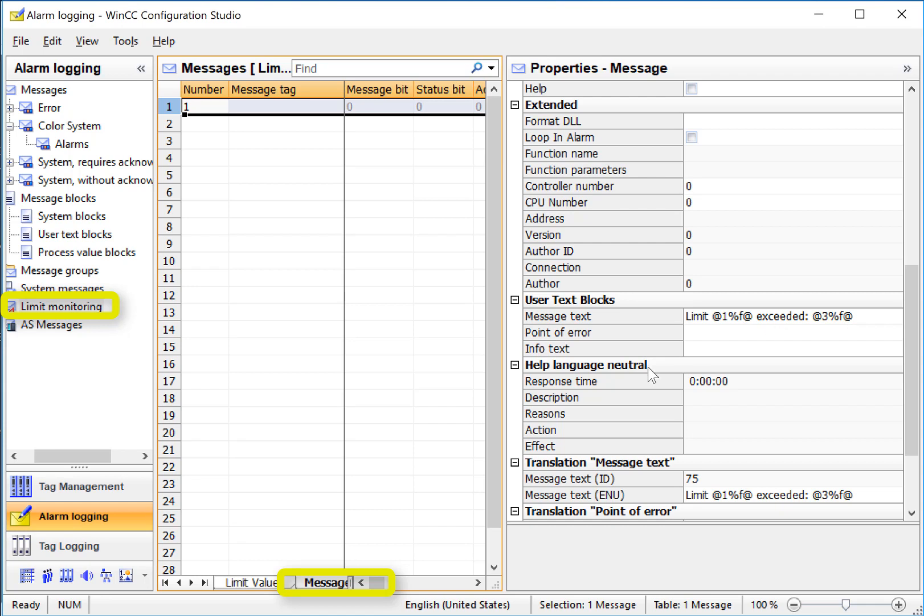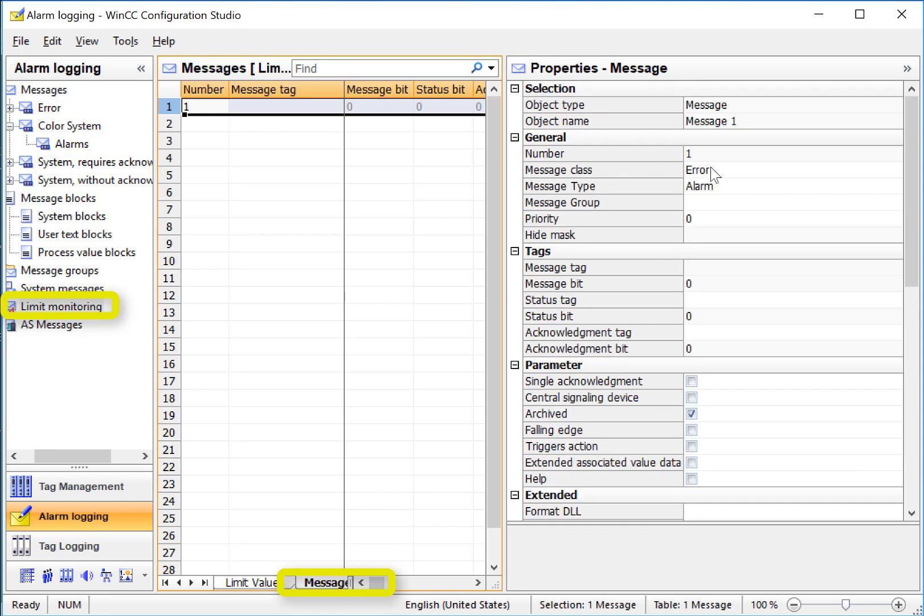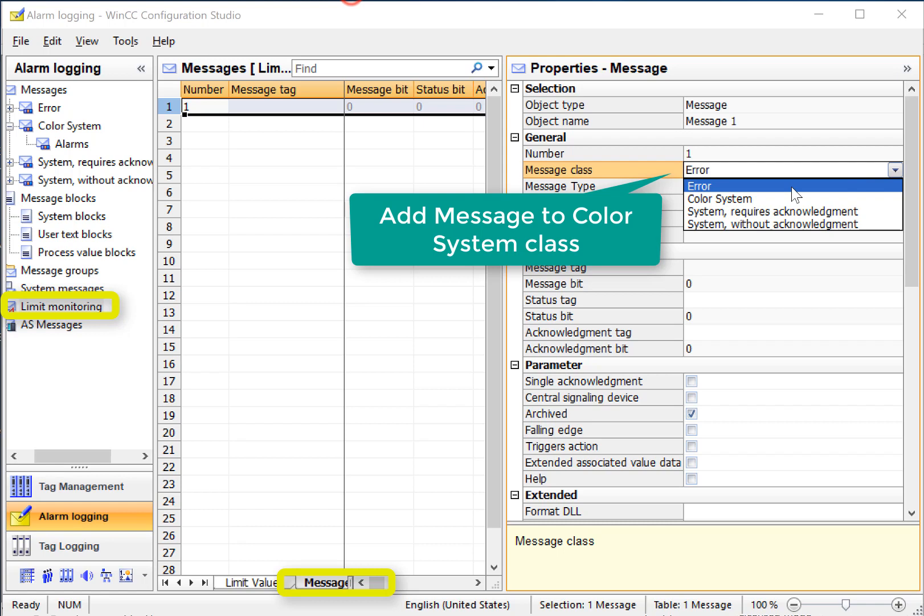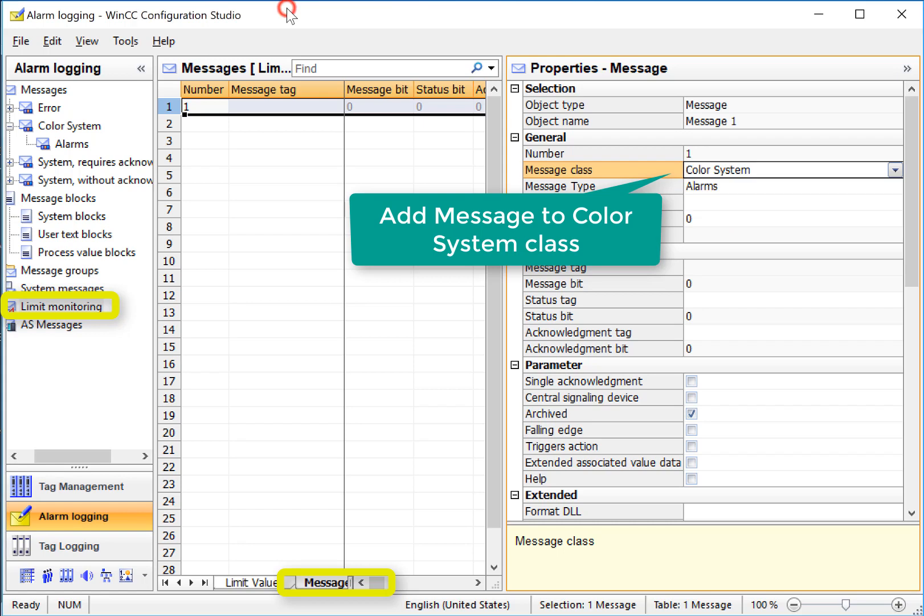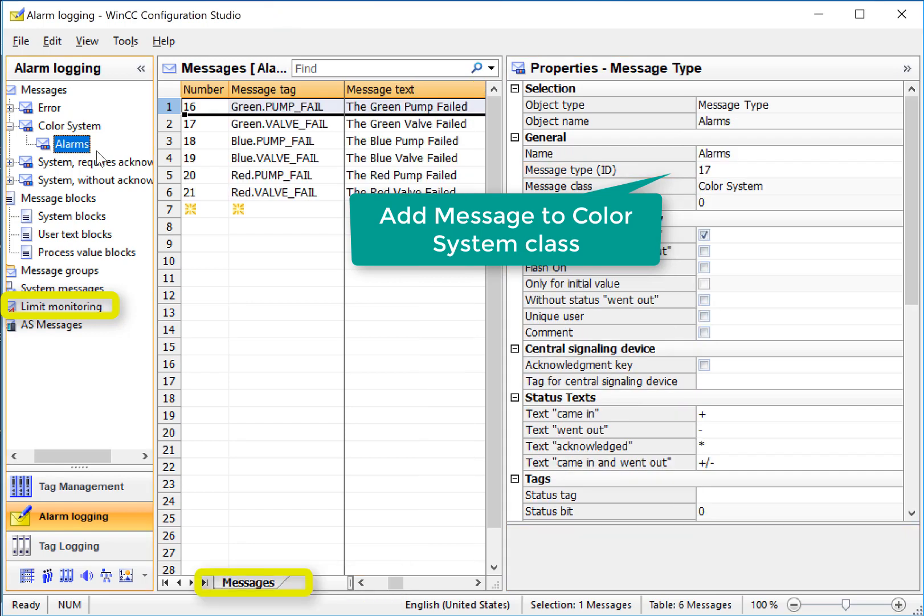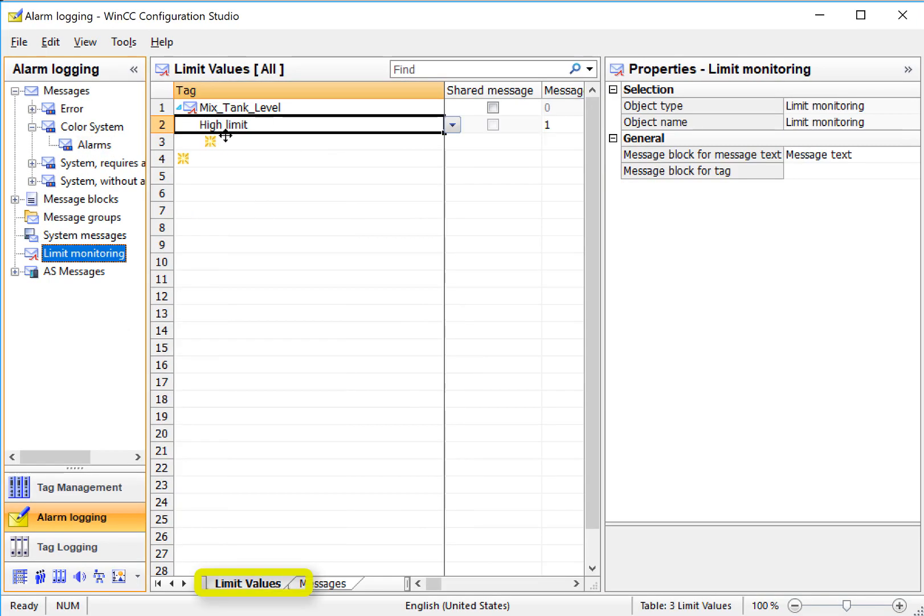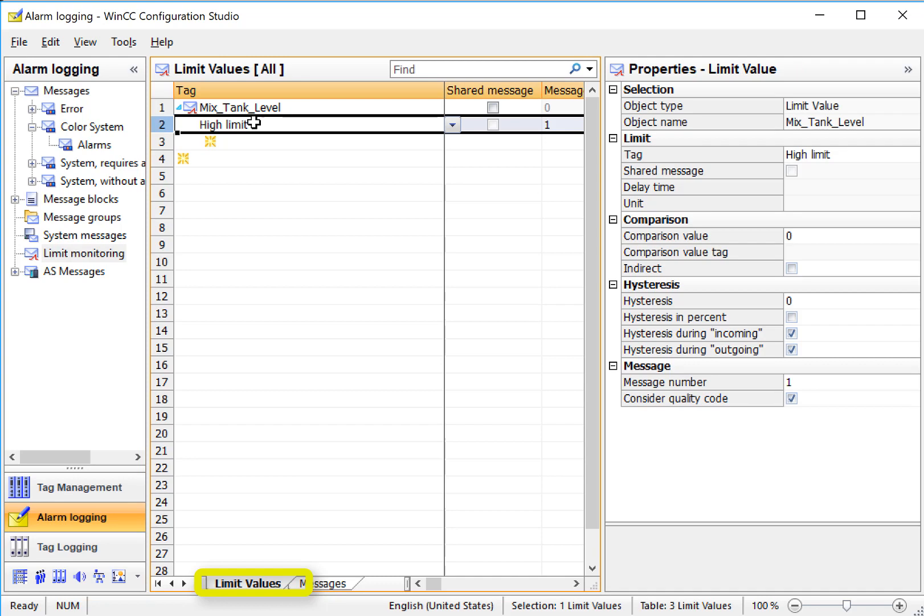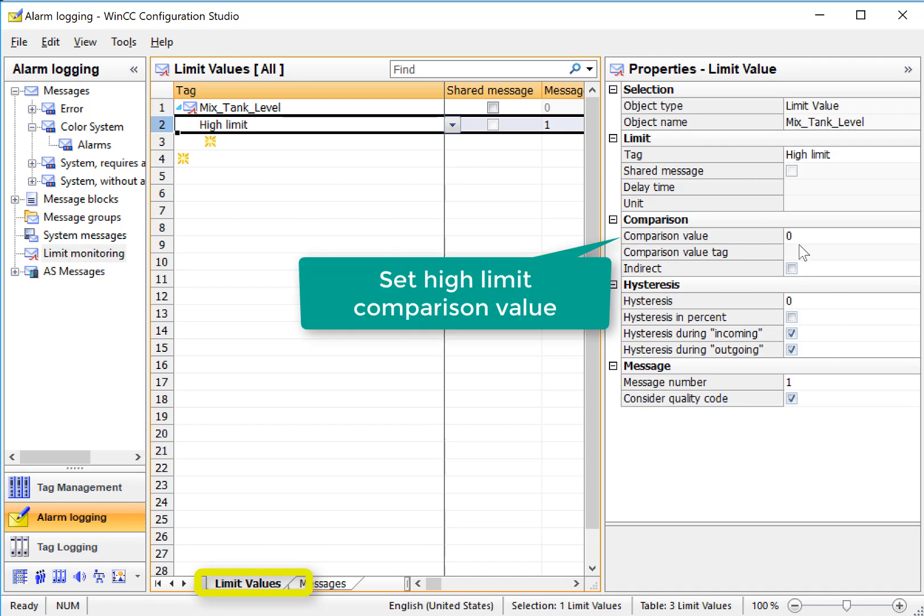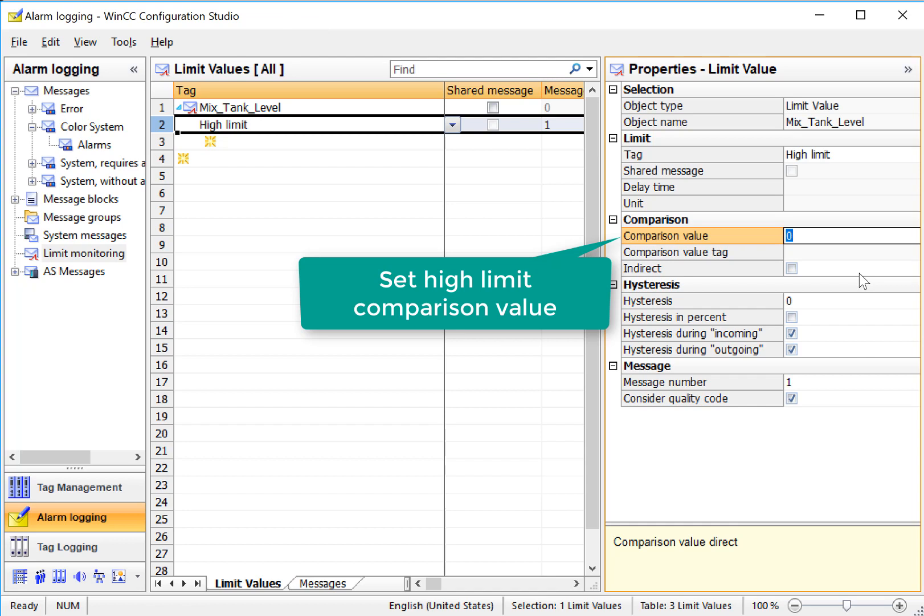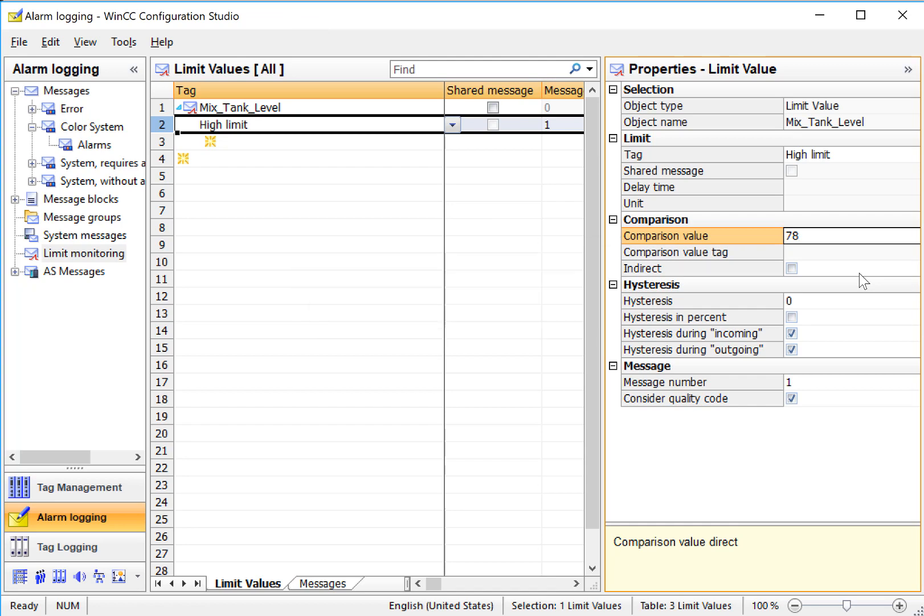Of course, you can change this if you want. We can also add this message to our color system class. And so it takes on the properties of our subclass. So it is going to be expected to be acknowledged. We'll also want to go to our high limit and set the value at which it alarms. So we'll set this at 78.